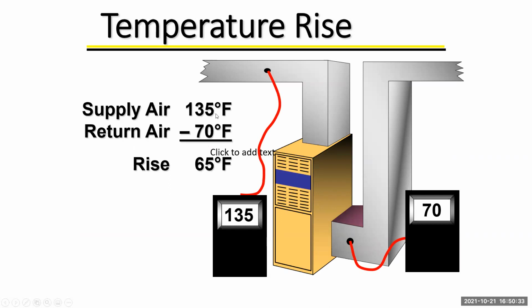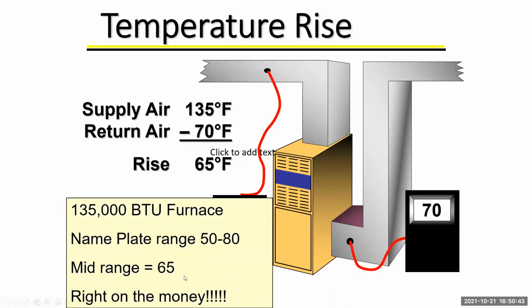Here we'll look at it. 135 supply, 70 returns, 65 supply, or excuse me, 65 degrees difference. That's your temperature rise. Most of our stuff is rated either 40 and 70 or 50 and 80. 65 is pretty good. Now, say you're rated for a 50 to 80 and you're at 79 degrees temperature rise. Don't say, oh, I'm below 80, I'm good to go. No, figure out your problem, because you're going to get above 80. So figure out where your problem is, whether it be airflow, dirtiness, whatever.